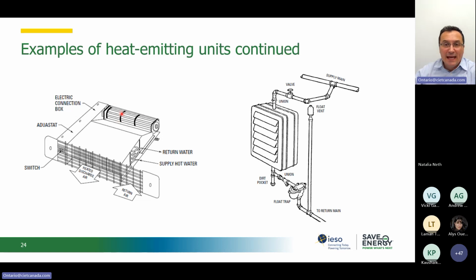picture. By adding a fan, we improve the heat transfer because now we have more volume of air passing over the coil and therefore absorbing more heat from the fluid that passes through the tubes of this coil. Or other forms of design, unit heaters, which are, again, a choice that we've seen in storage areas, garage, parking areas, sometimes loading docks, not necessarily in spaces occupied by tenants in multi-residential buildings.